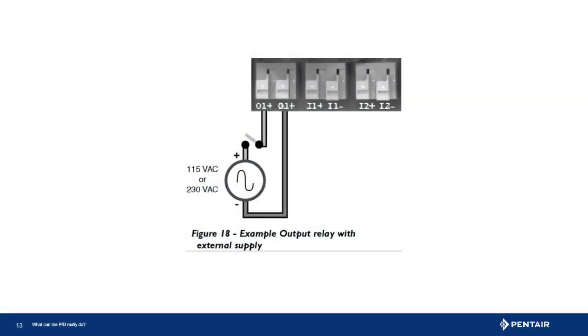A typical output is a warning light as diagrammed here. So, when programmed and wired correctly for a fault, when the drive goes into a fault condition and stops, the programmed relay will close, passing voltage to the light, giving an excellent visual that the drive is in a fault condition.